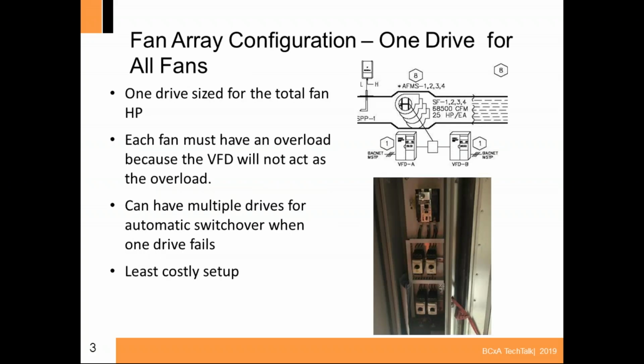Now, different types of fan array applications. This is a setup in which you have, on the right-hand side, a 4-fan fan wall, and they have one drive feeding the 4 fans. This drive is set at a horsepower equal to the sum of all these motors. That's kind of iffy to say, because you have startup and various other things that go into the size of this drive, but essentially that's what you're doing.